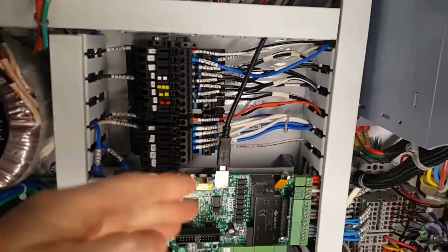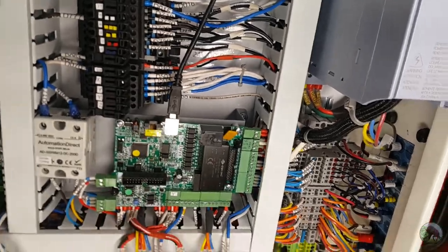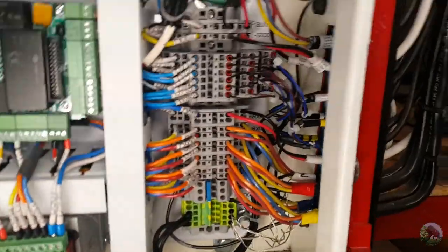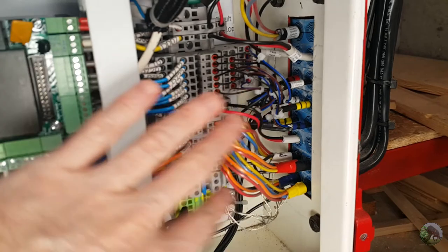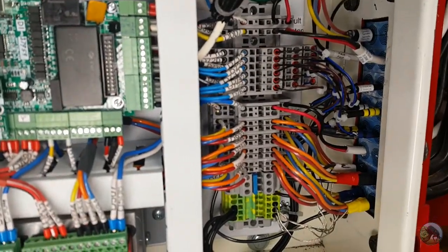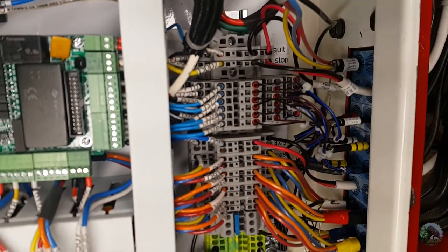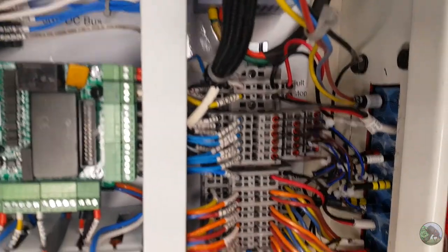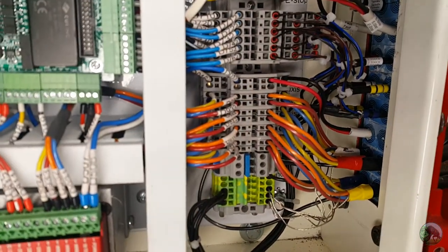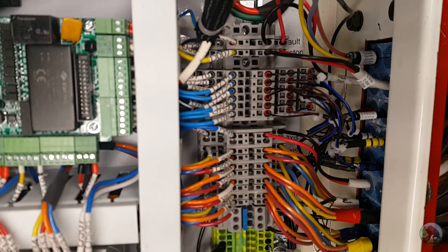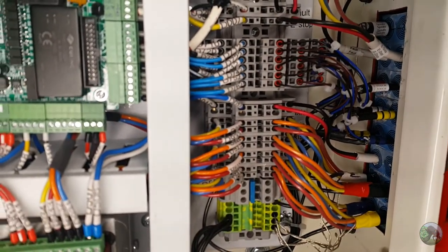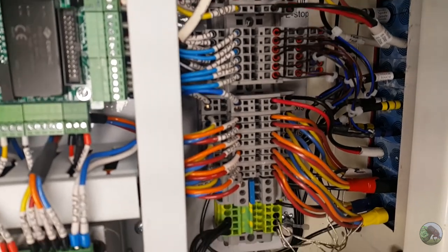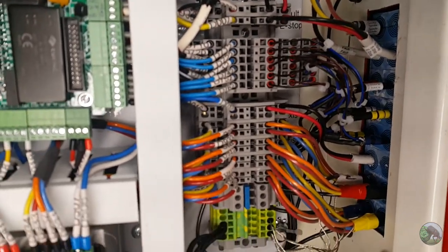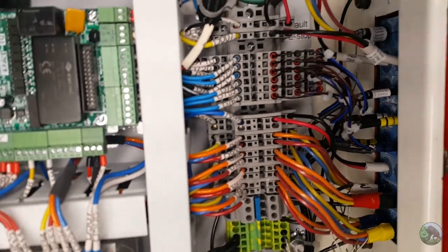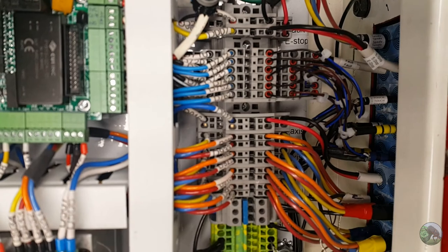So pretty much all these circuits go either to their destinations within the box, or they go to these field terminal blocks. So basically every wire that's coming into my controller comes in through right there and is attached to one of these field terminals. And theoretically, I guess you could delete this and just go directly to wherever you want, but I think it's best practice within a complicated box like this to have field terminal blocks like this, so that wires that leave the box have a clear and single location to come in. It's, I think, complicated enough without that. And so I think I'll leave it at that.